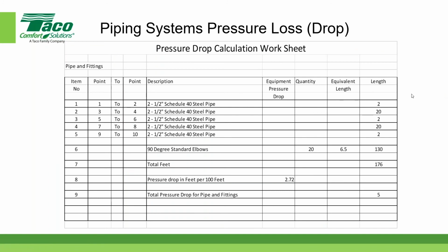And the reason I did that is because my piping diagram is somewhat schematic. I don't know the actual number of elbows that are going to be required to install this system. So I've increased my quantity from the 13 that I've shown in my diagram, and I decided to use a number slightly larger, 7 more than what I counted, allowing for some flexibility. And again, the equivalent length of each one of those elbows is 6.5 feet. And if you remember, going back to our chart, let's see if we can do this.